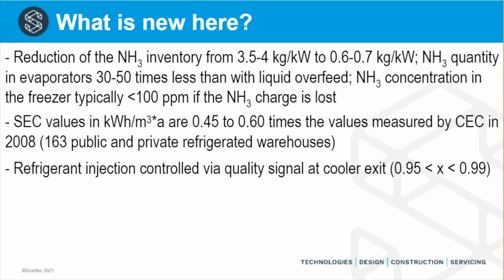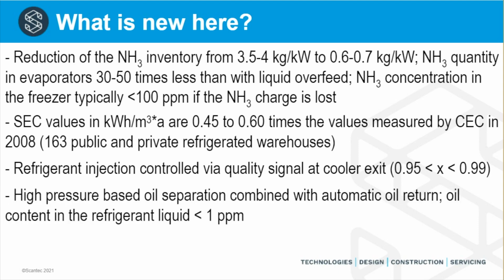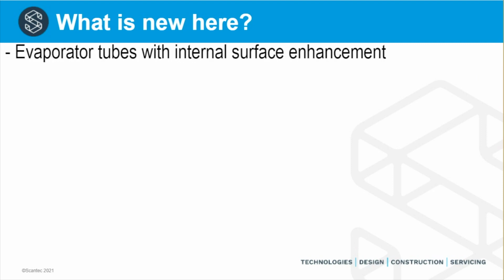I think I mentioned that we are operating at exit values, or X values, at the exit of the evaporator of approximately 0.95 to 0.99. This equates to 5 to 1% liquid in the vapor leaving the evaporator. I don't think I've explained all that much about the evaporator tubes and how important it is to pick the correct evaporator tubes. There are a couple of manufacturers in the world who are able to deliver stainless steel and aluminium evaporators with internal enhancement in the tubes themselves.